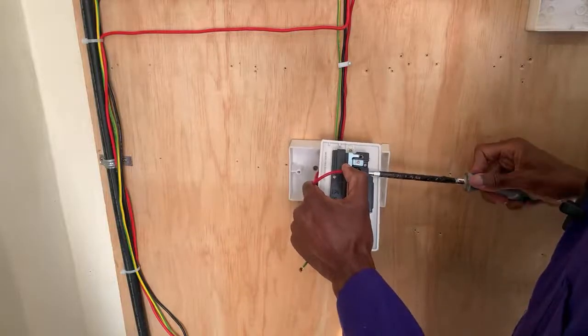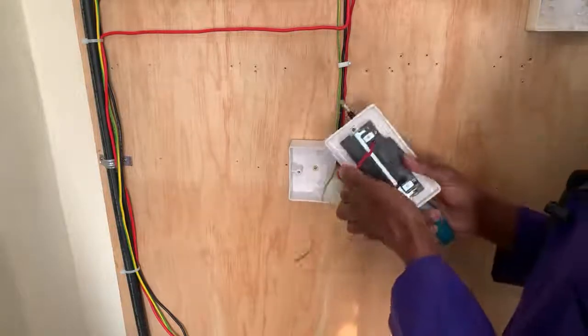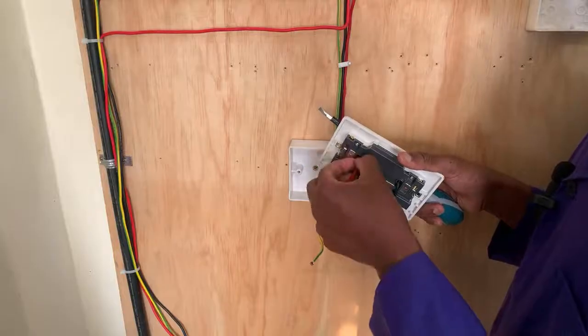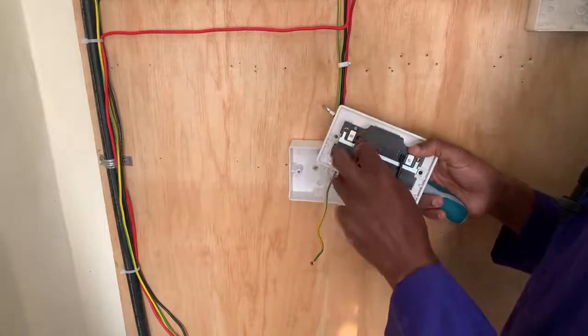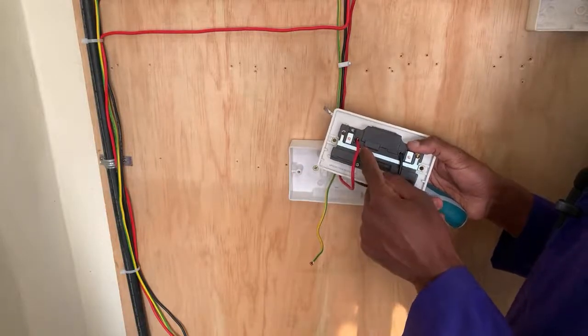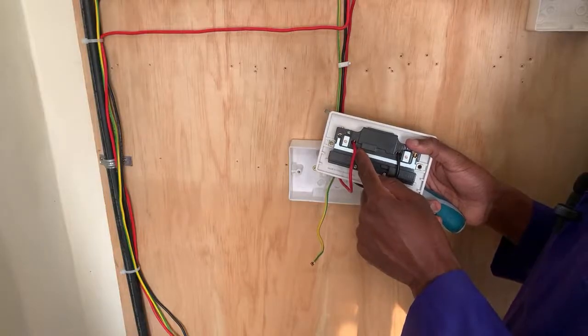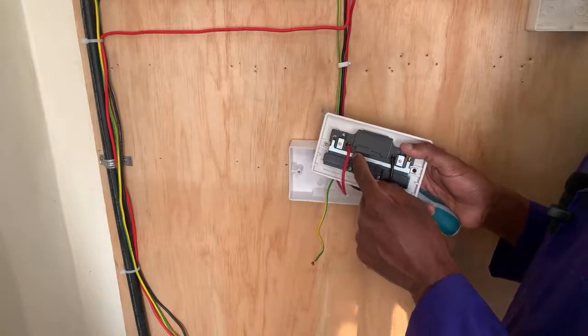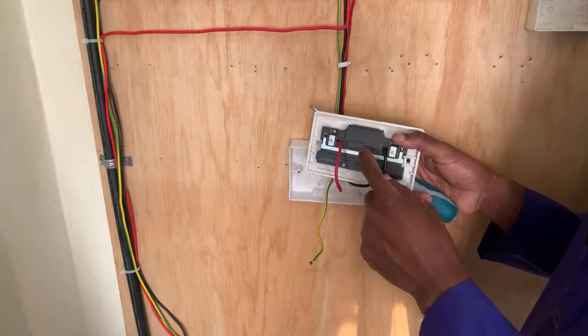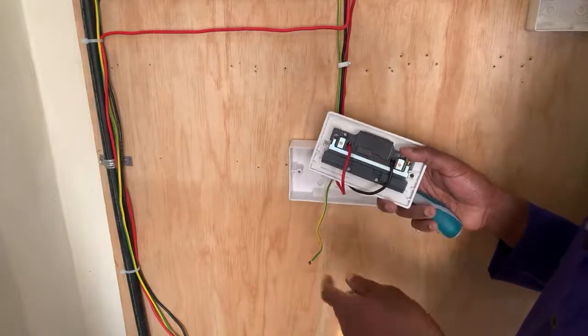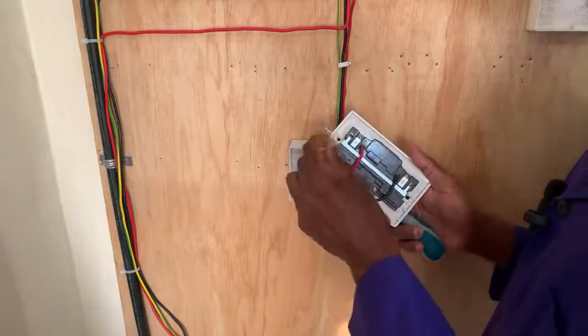Now here's another common mistake. If you don't let the whole insulation go in and it sags, it's a problem, because if it gets in contact with this earth connection here, there will be a short circuit. So you need to be really careful about that.